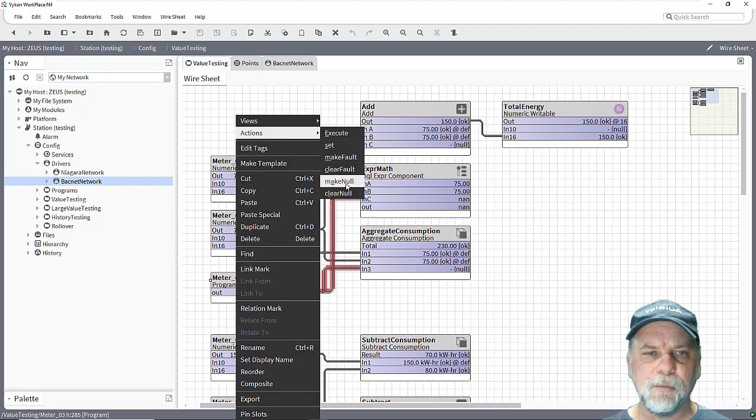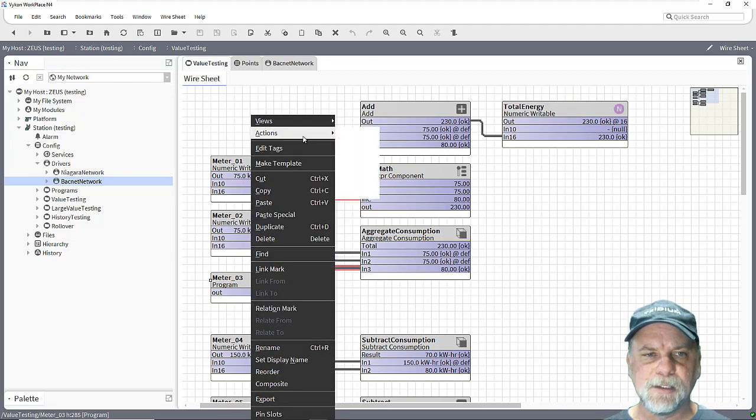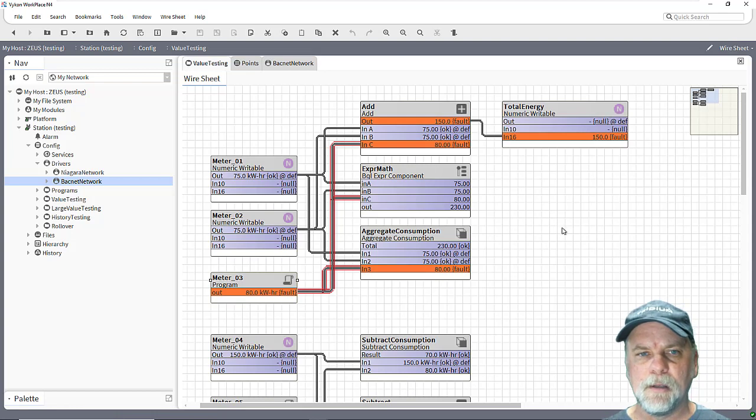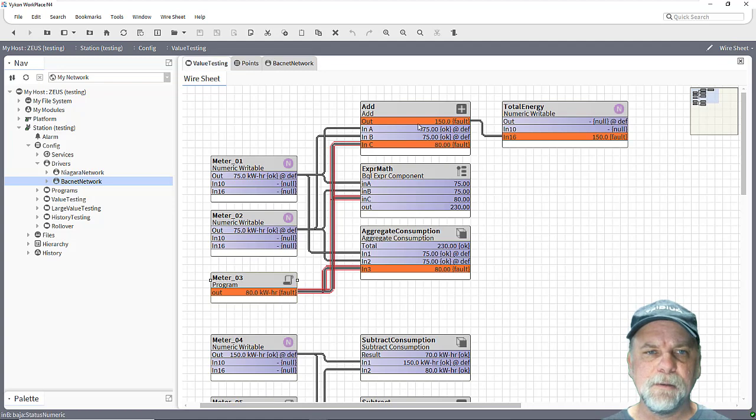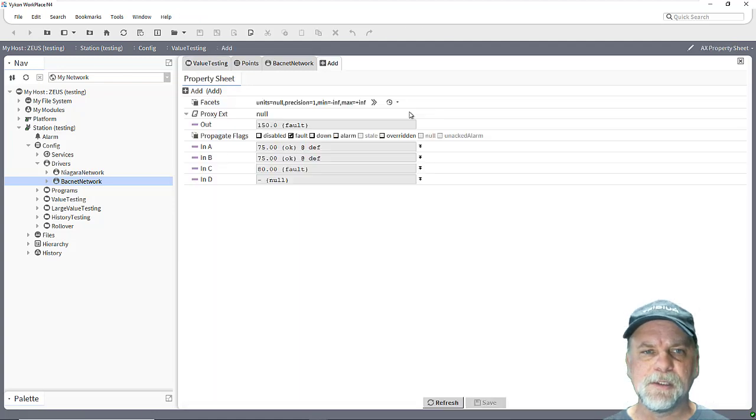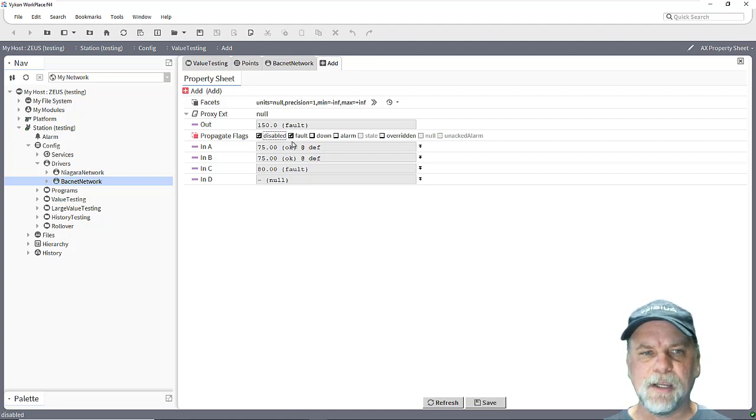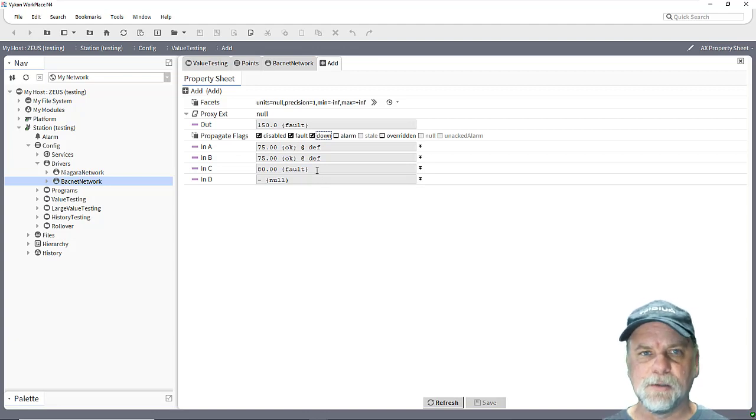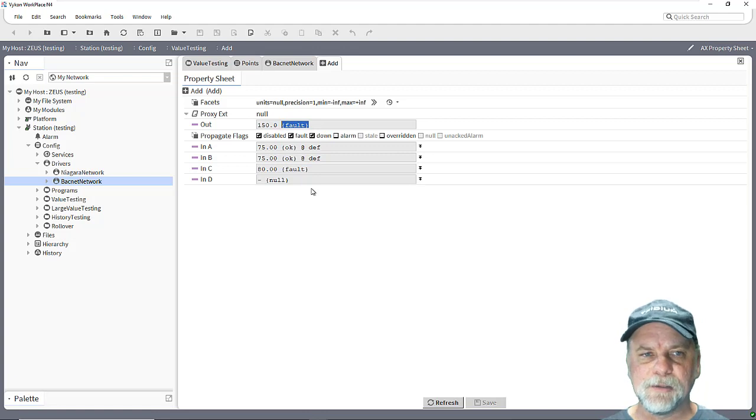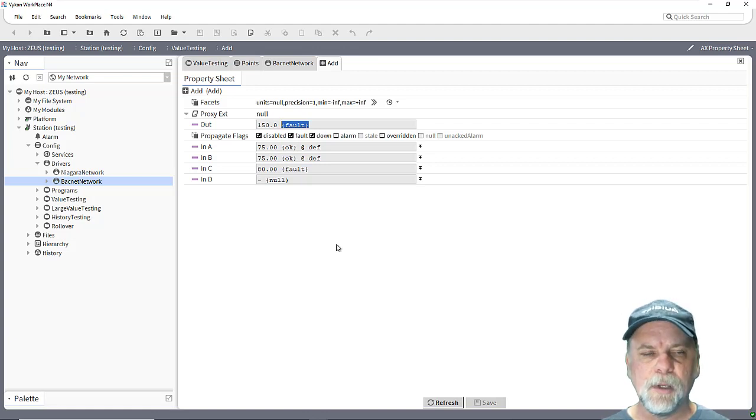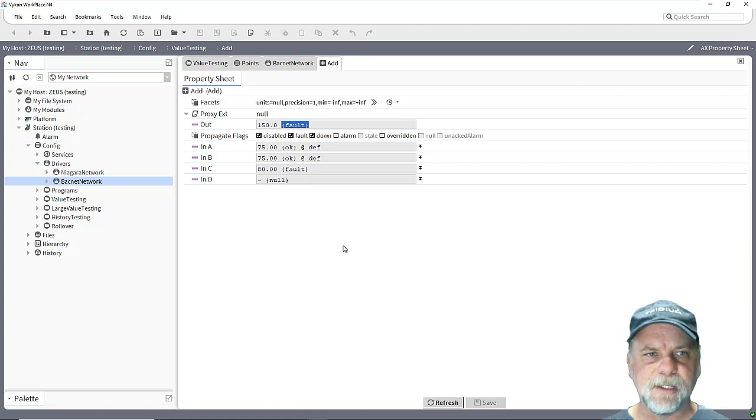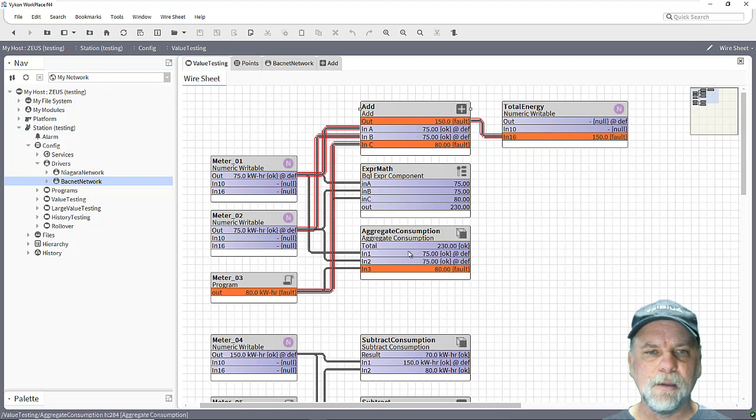Now another thing to keep in mind here is if we do have a fault status for example, how do we know that's there and is it impacting things downstream? And we can see looking at the property sheet of the add block there's propagate flags and by default none of these statuses are checked, but if I do check any of these statuses like disabled, fault, down and so forth, then if there's any of those statuses on the input slots that's also reflected in the output slot. So that's giving me at least some downstream indication that maybe I'm having some data integrity or data validity issues on the inputs into my control logic, or if I'm recording a history on this aggregated value then it also gives me some indication that the underlying source data sets might have some unreliable data condition in them.